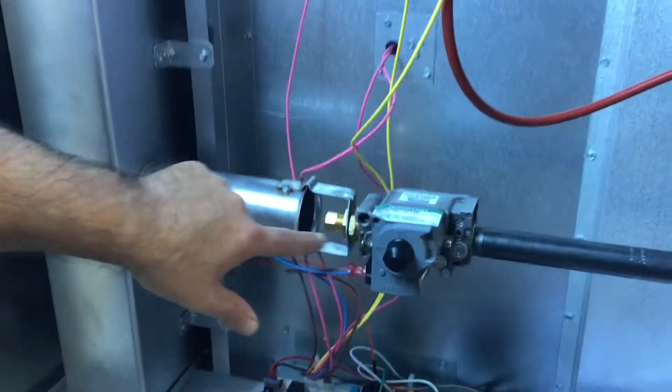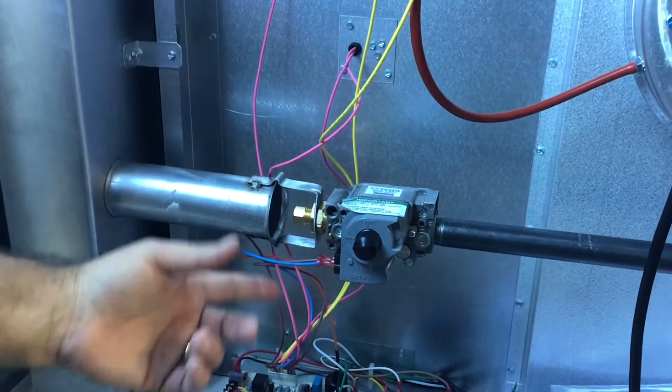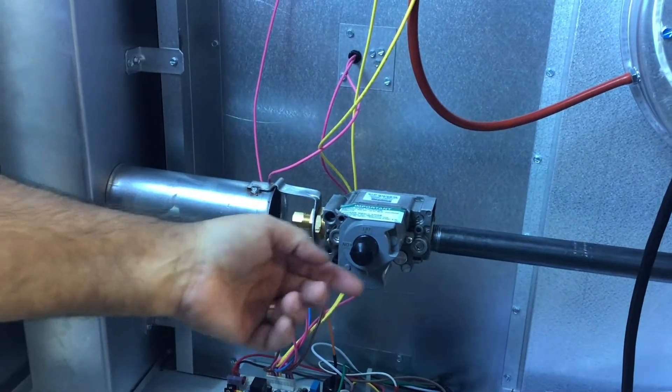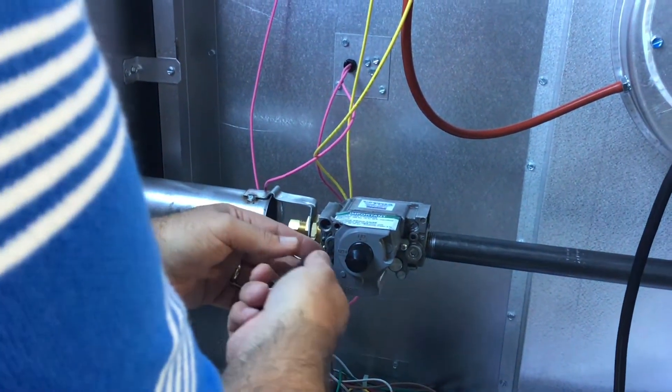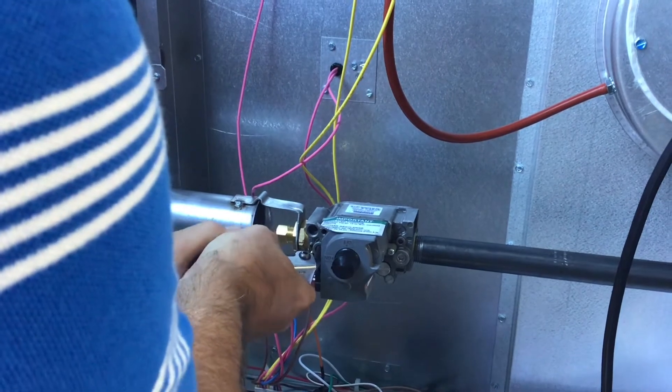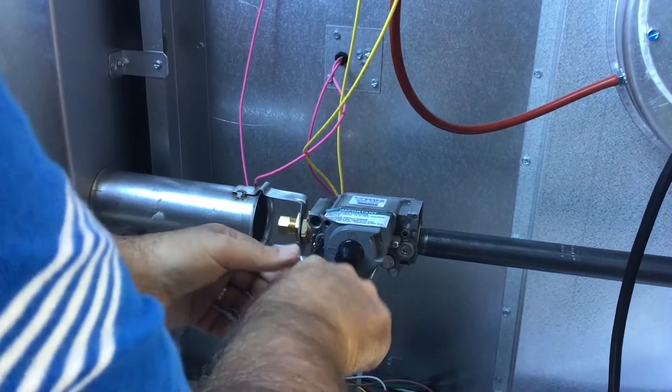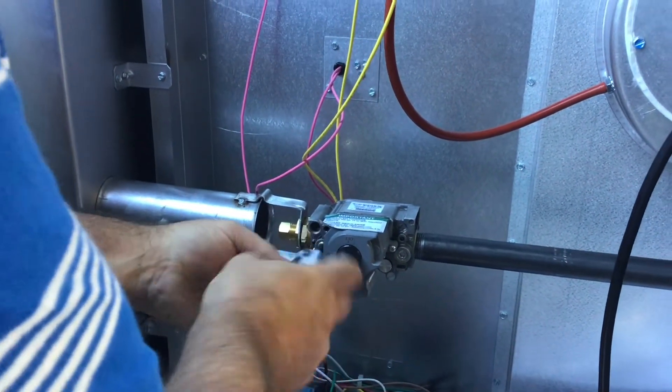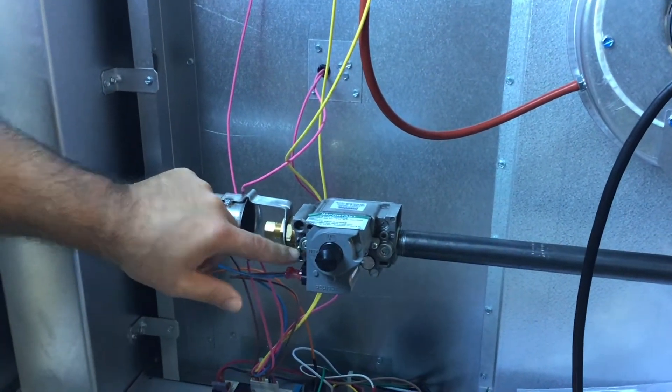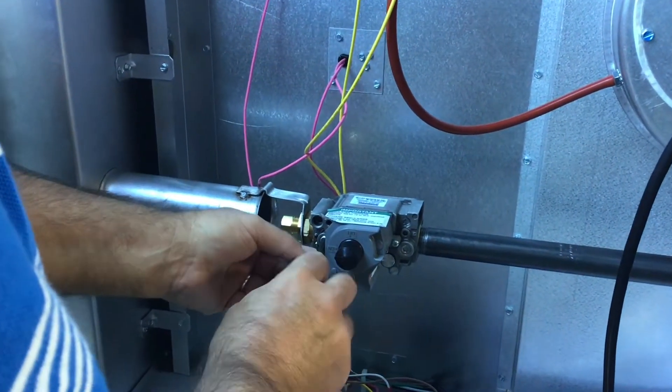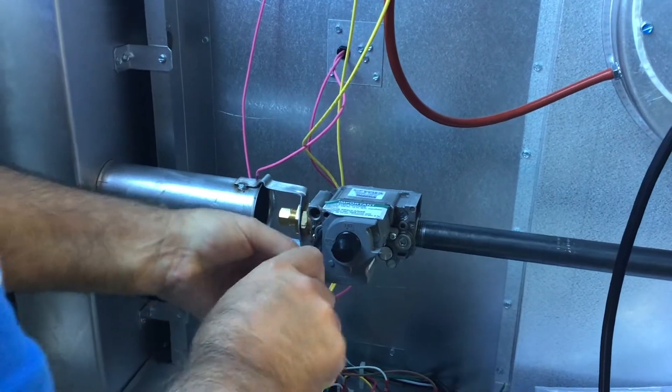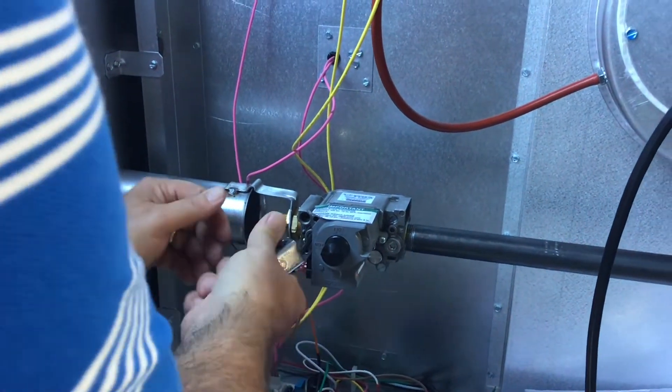Then we're going to check the outlet side and the way we're going to check the outlet side is we're going to have to actually run the unit but same principle here. Remove the Allen key, insert your manometer here and we're looking for 3.5 inches of water column when the unit is running.